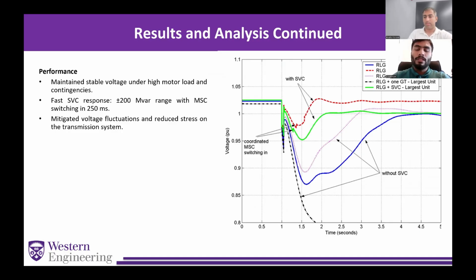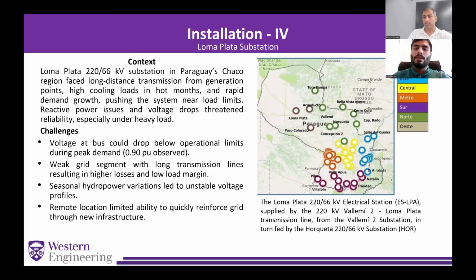Yeah, so in this simulation, we can clearly see that without SVC, the voltage was even below 0.9 per unit. It is not in the operable range. So with SVC, now the voltage is around 1 per unit, and it is in the operable range, and it has ensured voltage stability in the system. Can you go to the next slide, please?